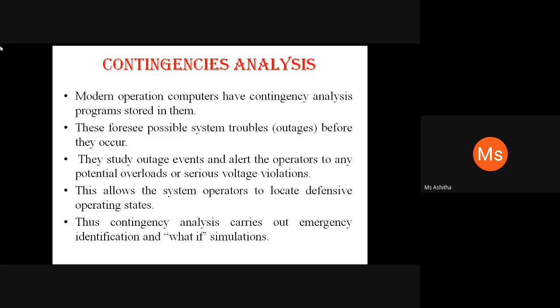For example, the simplest form of contingency analysis can put in standard LP programs along with the procedures to set up the load flow data, and this allows the system operators to locate defensive operating states where a single contingency event will generate overloads or voltage violations. This contingency analysis carries out the major emergency identification and what-if simulations, and solutions to the problem which occurs. So the identification process will be in the contingency analysis stage.